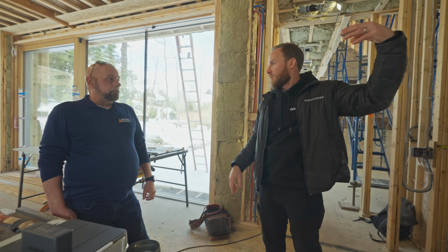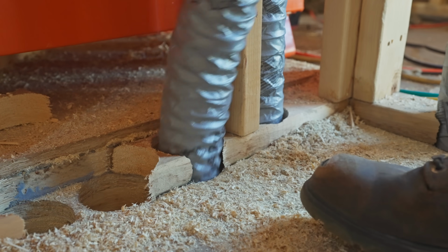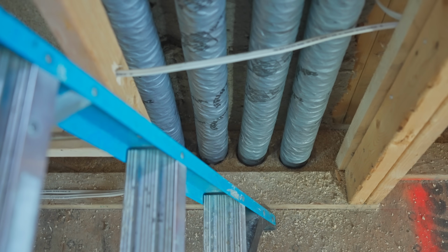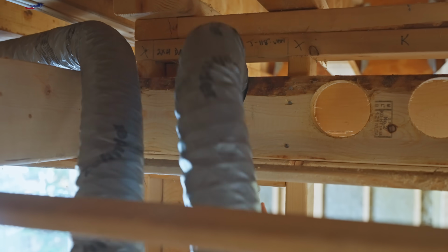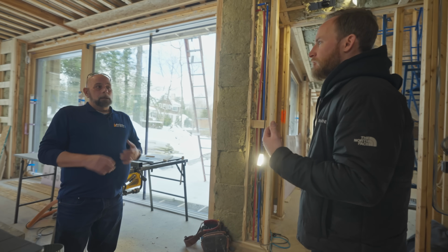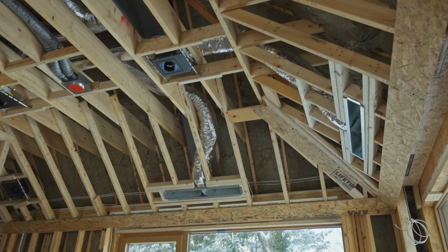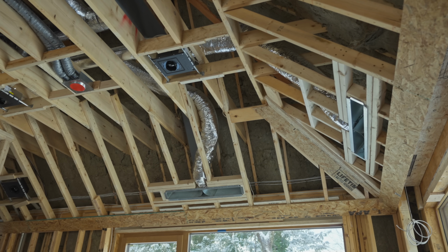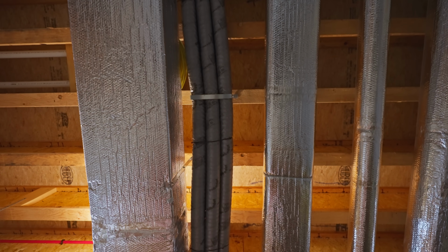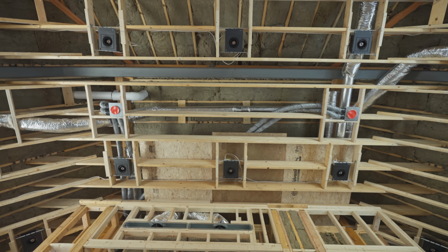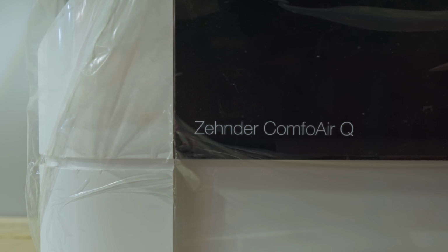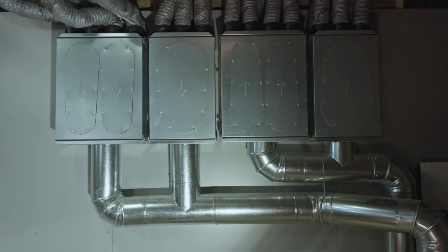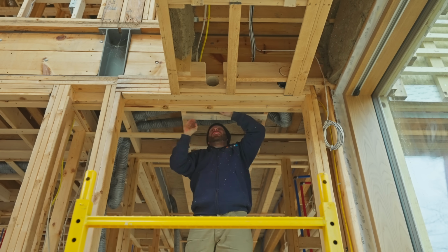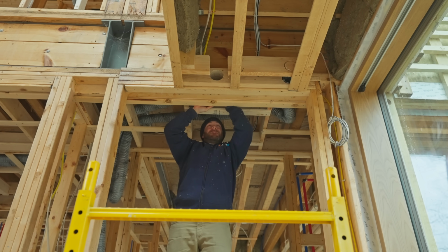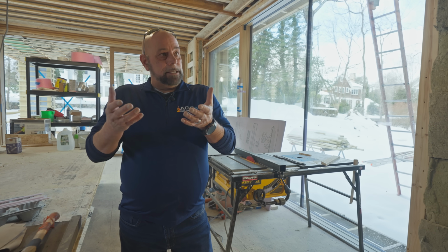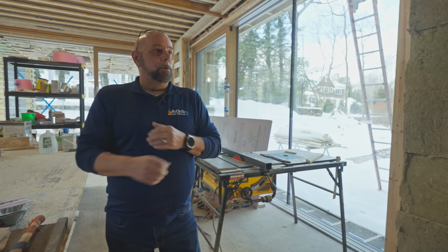These are extraction points, right? Correct. In a kitchen area, you're typically just extracting because there's a lot of stale air and people hanging out cooking. So you want to get air out of this space, but provide fresh air down in the living room and similar spaces where you're hanging out most of the time. Kitchen, you extract. Bathroom, you extract. Laundry room, you extract. The Zehnder system is capable of keeping a certain amount of air always moving and changing in the house. As bathrooms or kitchens are used, it brings the blower motor up to increase the air, whether extracting or putting fresh air in.